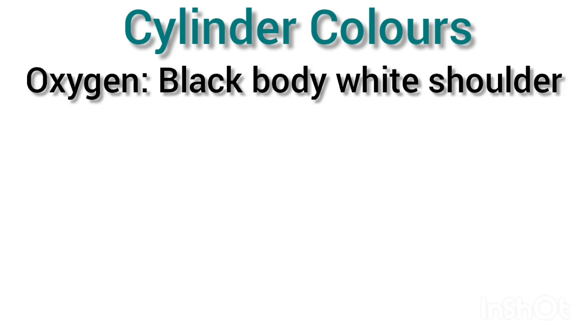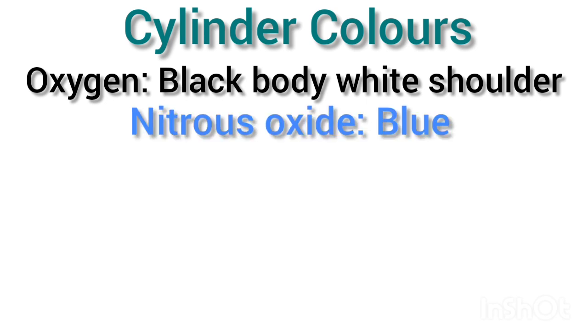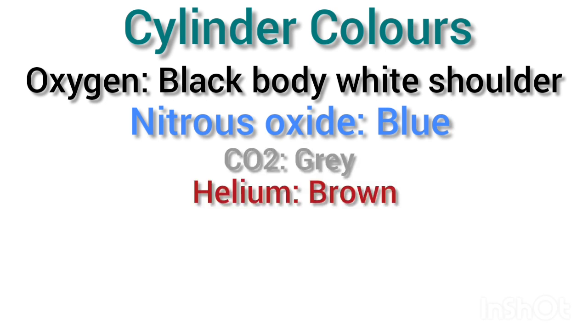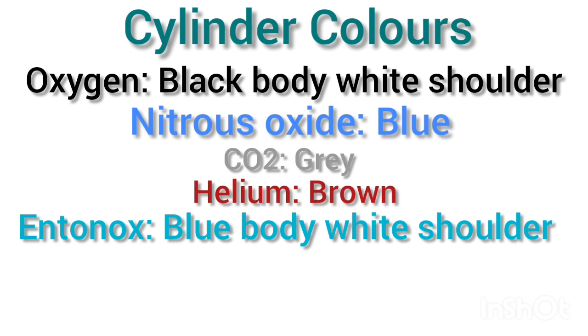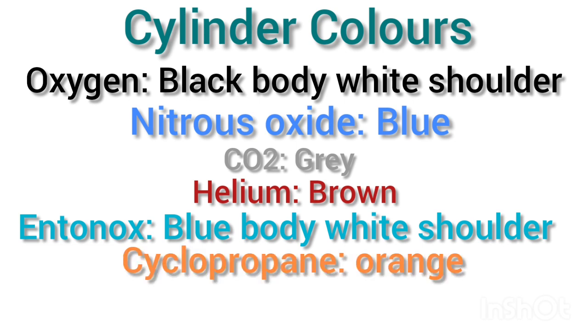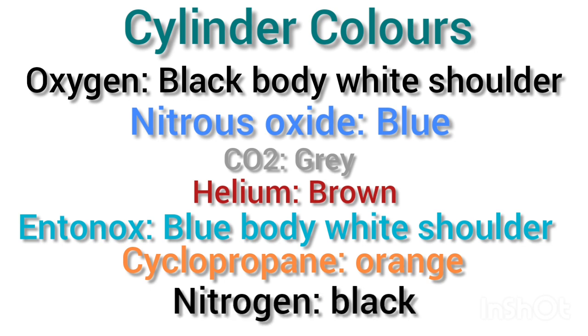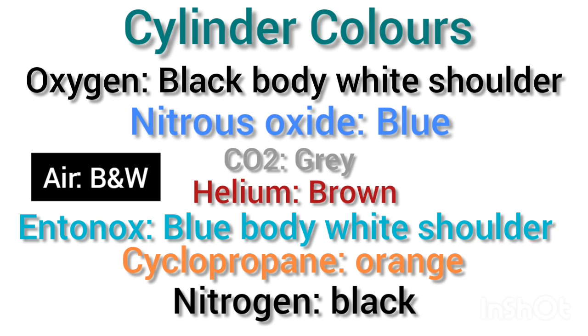Different color systems are used for different gases: black body and white shoulder for oxygen, blue for nitrous oxide, gray for carbon dioxide, brown for helium, blue body and white shoulder for Entonox (a combination of oxygen and nitrous oxide), orange for cyclopropane, black for nitrogen, and black and white for air. Suction is usually coded yellow.